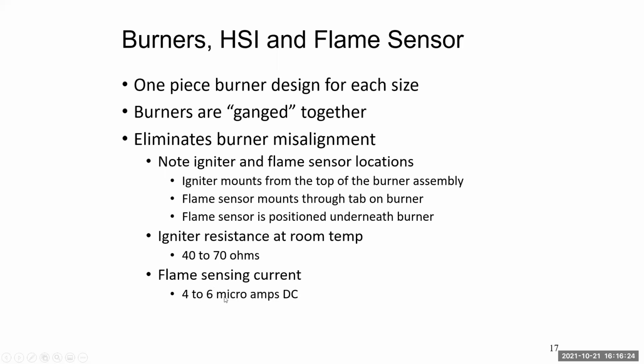Make sure you physically check your flame sensor before you throw another one in there, because I've had it the last couple times in the last few weeks. Guys say, I got a bad flame sensor, and they put another one in, and still got the same problem. Now they're throwing a board in. So unless you want to eat the cost of parts, because we all know it's a correct thing to just throw parts in and charge your customer for whatever we put in there. Save your customer, and use some time and effort and just check it real quick. If you don't have a meter that checks microamps, get one. Like Craig talked about, having the proper tools for the proper jobs.